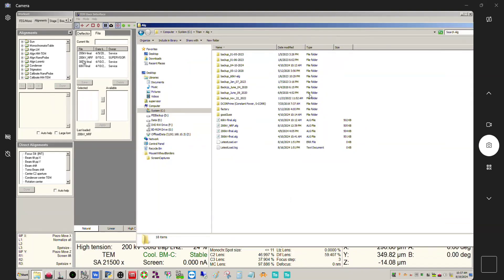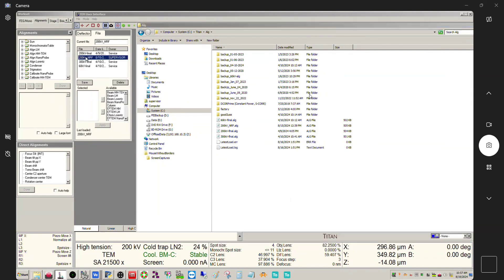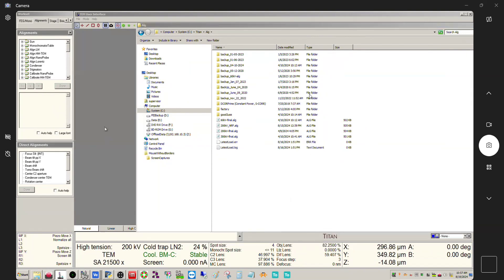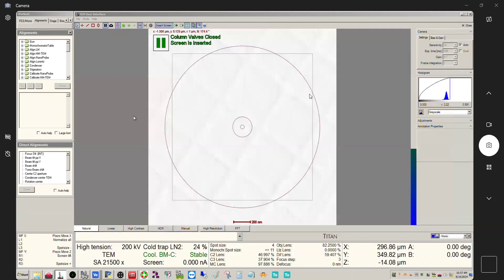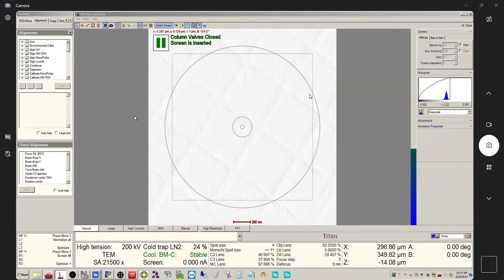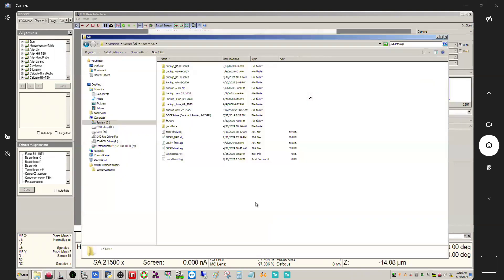Yeah it's a good thing to do, especially if you're logged in at the supervisor level because unfortunately somebody who's careless could very easily delete this or overwrite it or cause a problem. We wouldn't be ordinarily logged in at the supervisor level, but the reason we are is because we can't get the GIF to talk to the microscope properly unless it's logged in at supervisor level. That's a necessary evil with the Talos. We don't have a GIF on that so for general use that is only logged in at the user level so we don't have an issue. We only use the supervisor account when we're doing maintenance on the machines.